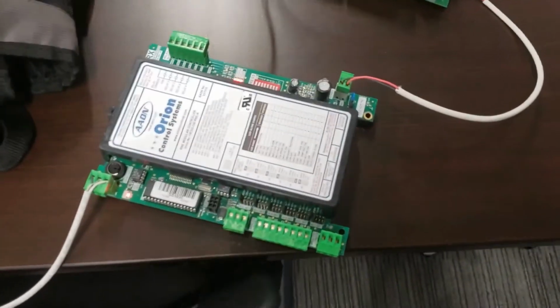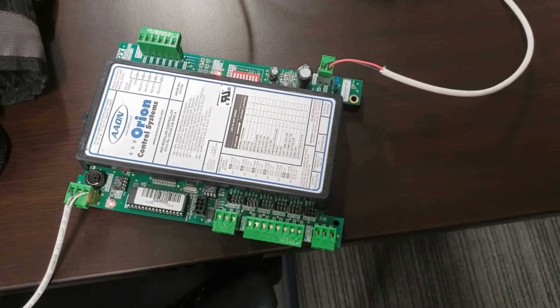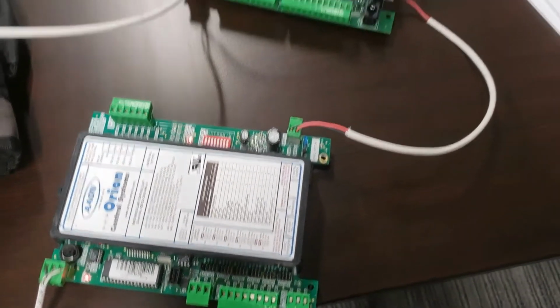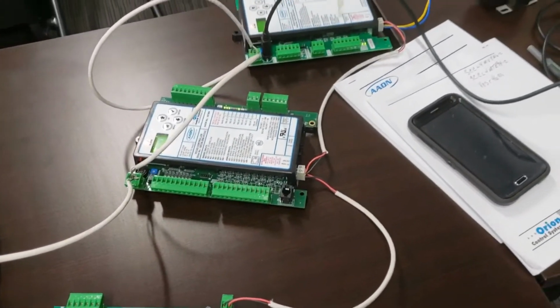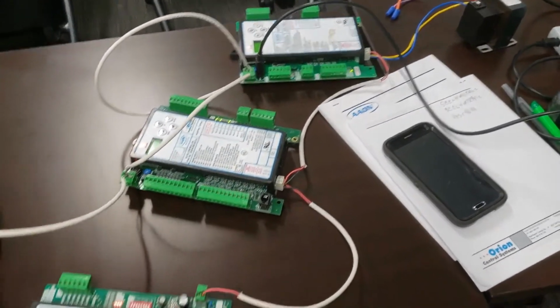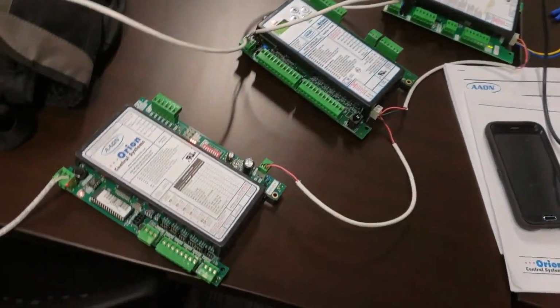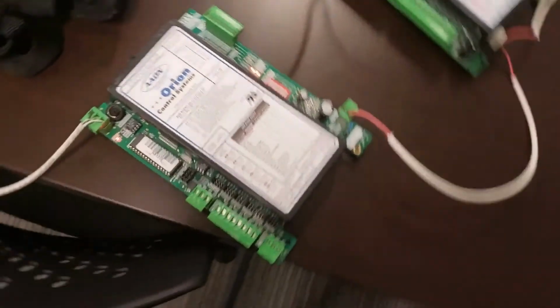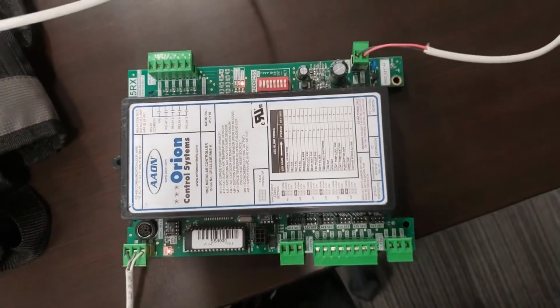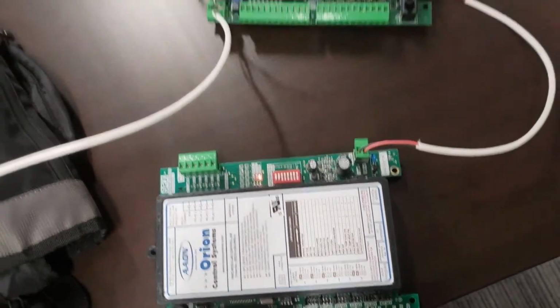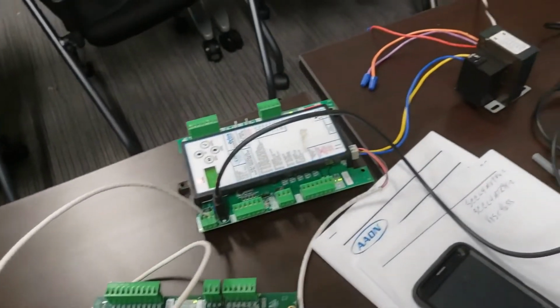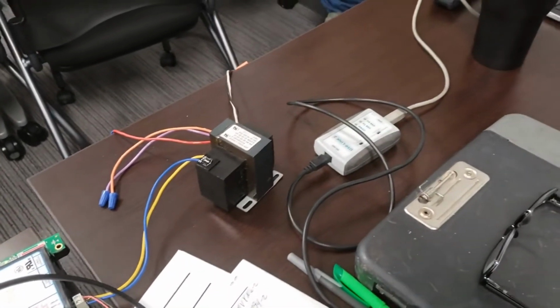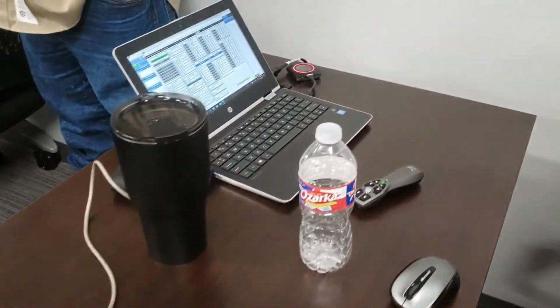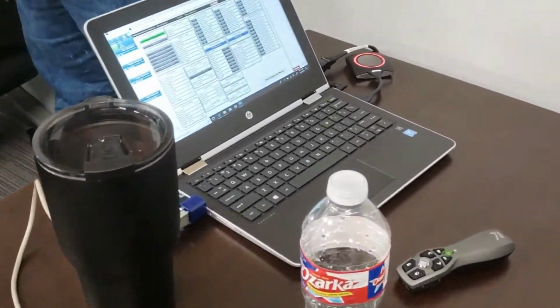If the lead compressor burns out, does that shut down the whole system? Can you bypass it and let it run for a duration? You could. If it's your lead compressor and it's got hot gas reheat, I would take my suction pressure transducer and move it over to compressor number 2, fire it up and run. That can give you time to get the compressor to release a little bit of cooling.